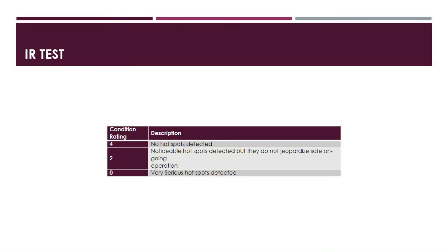The fourth category is the infrared testing, also known as the IR test. This category has only three ratings: 4, 2, and 0. A rating of 4 means no hotspots are detected. A rating of 2 means noticeable hotspots are detected but they do not jeopardize ongoing operations — it does not lead to an unsafe operation. A rating of 0 means very serious hotspots are being detected in this test.